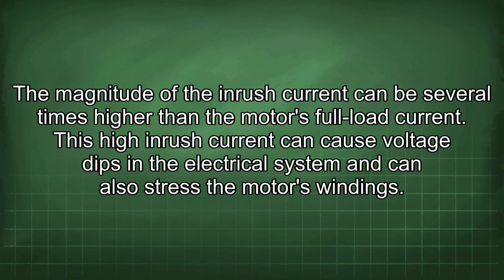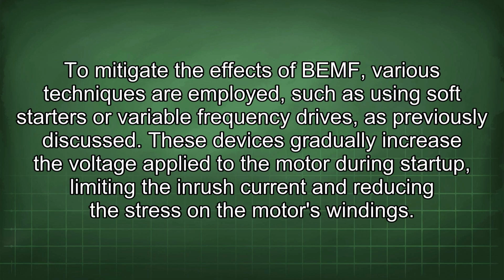This high inrush current can cause voltage dips in the electrical system and can also stress the motor's windings. To mitigate the effects of BEMF, various techniques are employed, such as using soft starters or variable frequency drives, as previously discussed. These devices gradually increase the voltage applied to the motor during startup, limiting the inrush current and reducing the stress in the motor's windings.